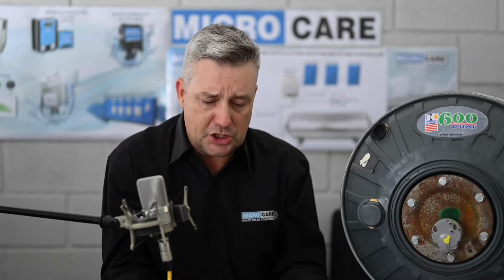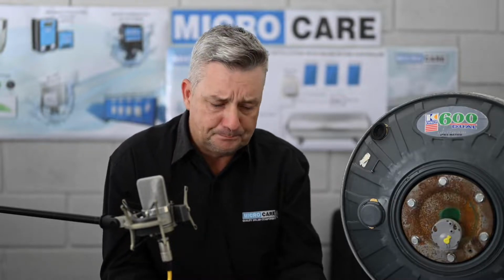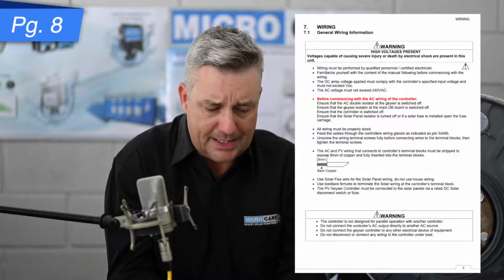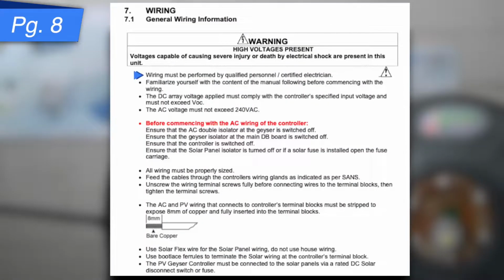And then the last section to cover here before we look at the thermistor, some general wiring information. Please, we request that it's done by qualified personnel or a certified electrician. Familiarize yourself with the contents of this manual before you go ahead. Now, the DC array voltage applied must comply with the controller's specified input, and the voltage, as mentioned, must not exceed the open circuit voltage.